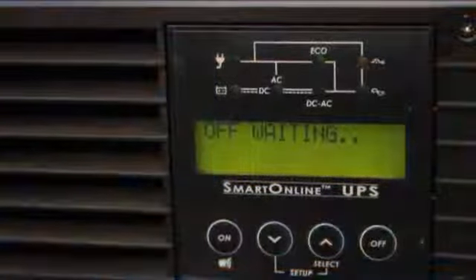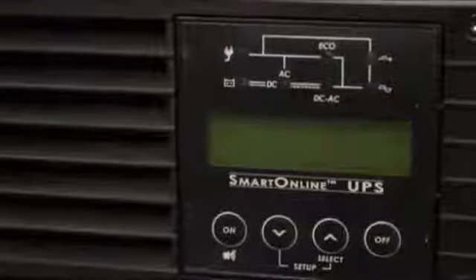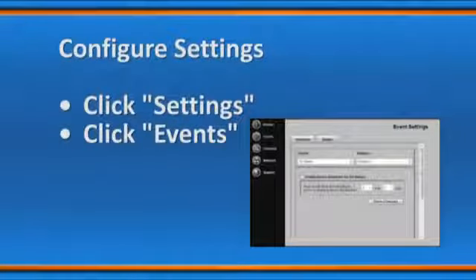Change UPS shutdown settings if desired. During a power failure, the SNMP web card is pre-configured to shut down the UPS system 2 minutes after receiving a low battery signal. This allows the UPS system to provide the maximum available runtime to connected equipment. To change settings, click Settings, then Events. Highlight Low Battery and Shutdown and alter desired settings.